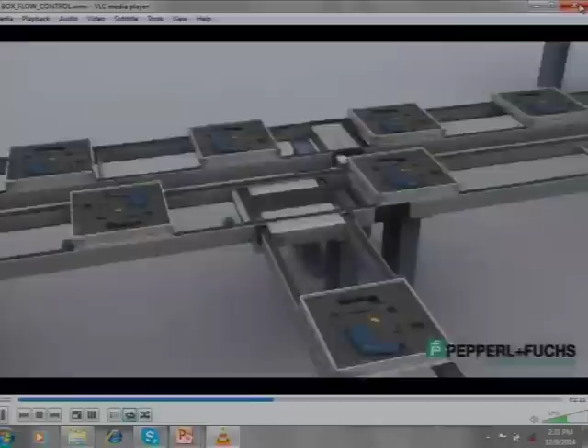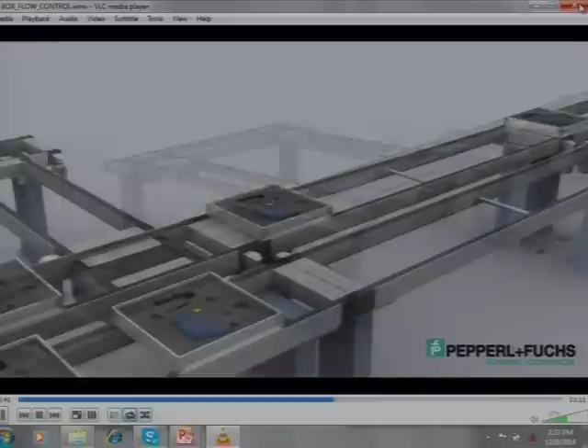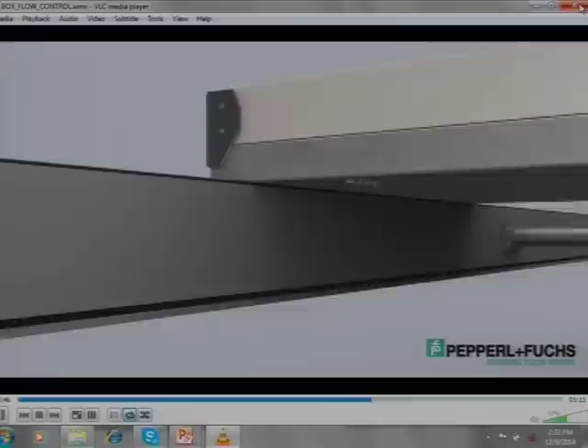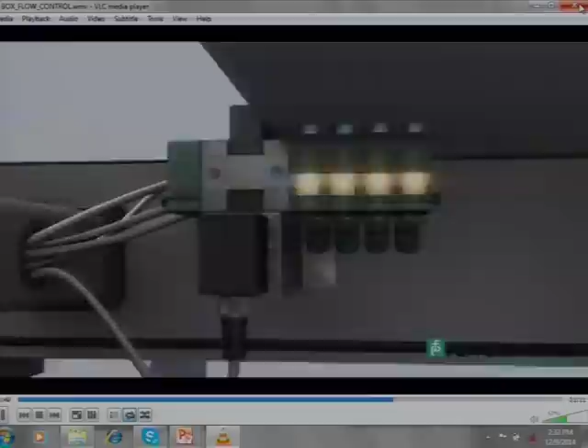Now there are certain applications in the industry where you require sensors which have some special features. As I said, industry may not have mild steel as a target every time. The target can change. It can be mild steel, stainless steel, brass or copper. For that purpose, there are sensors which give a sensing distance of 10 mm, for example, with all types of targets. Those sensors are called reduction factor 1 sensors. That means irrespective of the target composition, the sensing distance will always remain the same. Your component can change from brass, copper, mild steel, stainless steel, anything. You don't need to change the sensor. The same sensor will give you the same sensing distance.